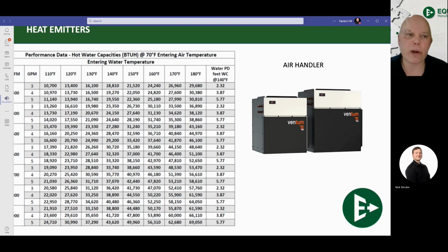And then I go back to my pump curve. I find something that is 4 GPM at, let's just say, about 12 feet of head. And that's how we size our circulator for our heat emitters. Quite simple once you've done it 100,000 times like I have, but I can understand that this might be a little confusing for you the first time. Basically, what I'm asking you to do is use the charts. They are your friends to at least tell you your head loss through your heat emitters, and you can figure out your distribution pipe afterwards.